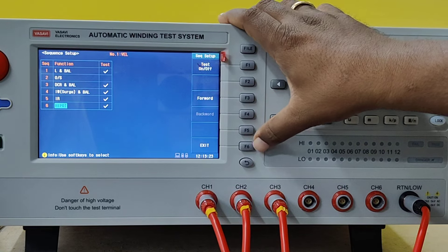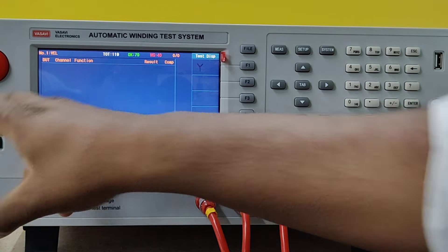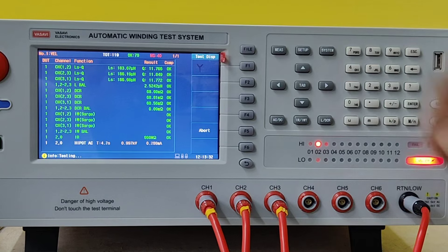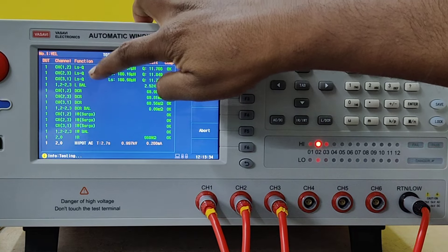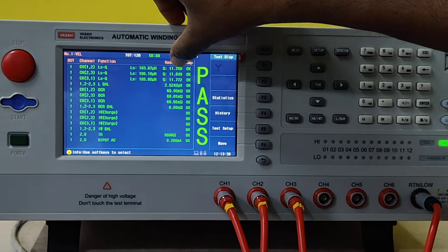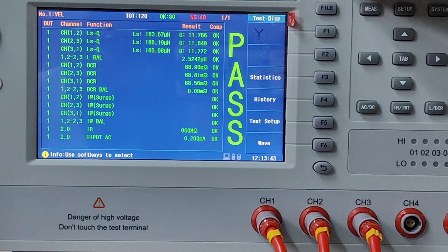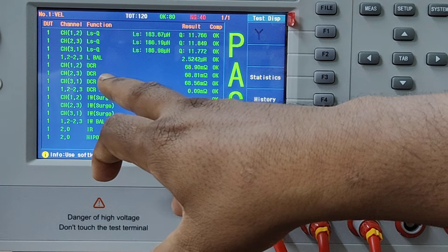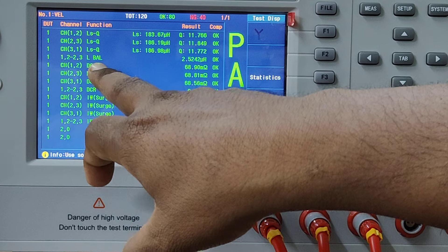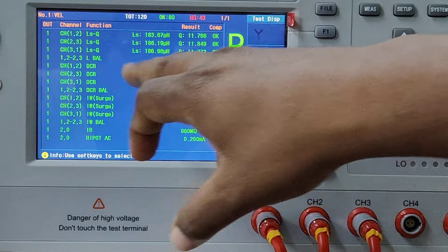Once all the parameters are set, go to the Measure button. The system is now testing all the parameters — you can see inductance for the first three, one for each of the three phases. Inductance measured value: if the value is within the limit, it will show pass. You can also see inductance balance between phases 1-2 and 2-3. Between these two phases it checks the balance, and if it is within the limit, it gives pass.